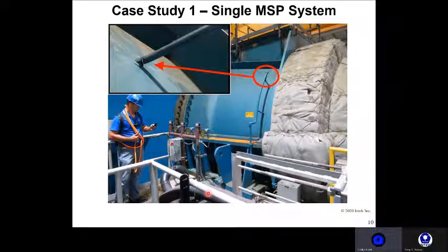This unit also had leaks at the expansion joint and surrounding a drains tank that accounted for the remaining 20 SCFM. The drains tanks at this plant have a history of issues due to high vibration and extreme temperature swings that have caused stress cracking in the tank bodies.